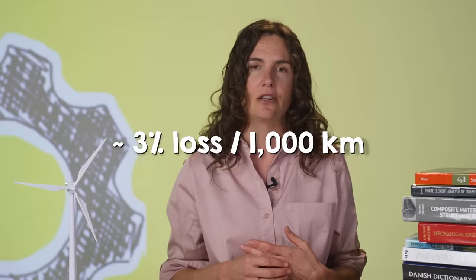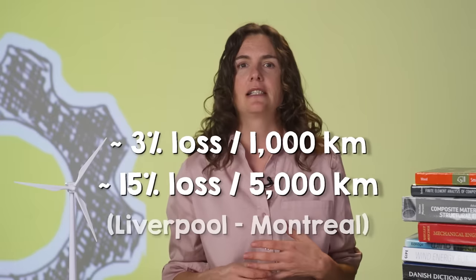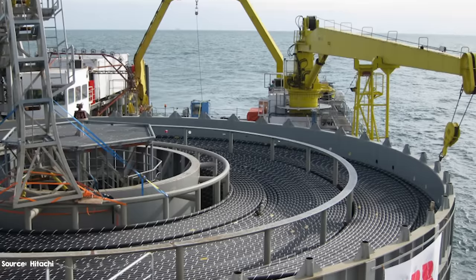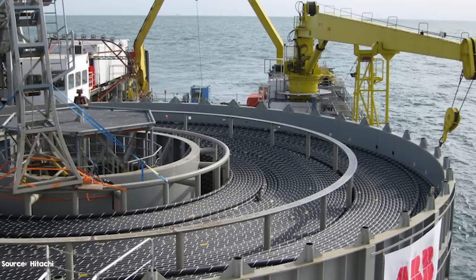Although DC is far more efficient than AC for long distances, there are still losses. Typically, an HVDC cable will encounter around 3% electrical losses per 1,000 kilometres, and across extremely long distances this adds up. To minimise these resistive losses, you have to make cable cores thicker.